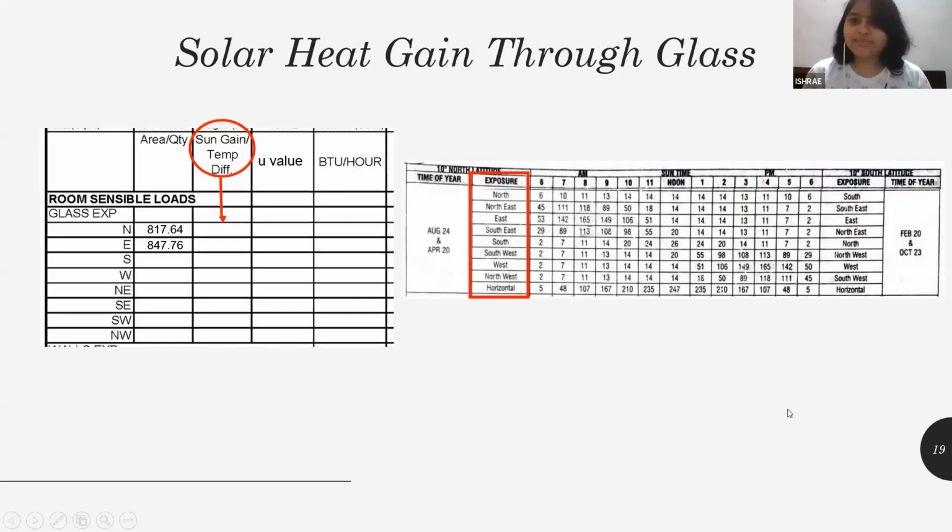What happens is sometimes architects want to be all creative and all, and they want to use daylight. So what they'll put is the skylight up on the roof. Instead of keeping a normal roof, they'll make a skylight. You may have seen it in malls, they have a skylight there. So in such cases, when you have a horizontal glass, that time the solar heat gain is different as compared to vertical glasses. So that time you all can use this horizontal value.